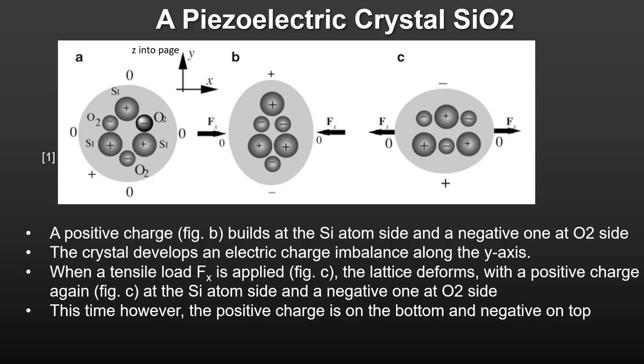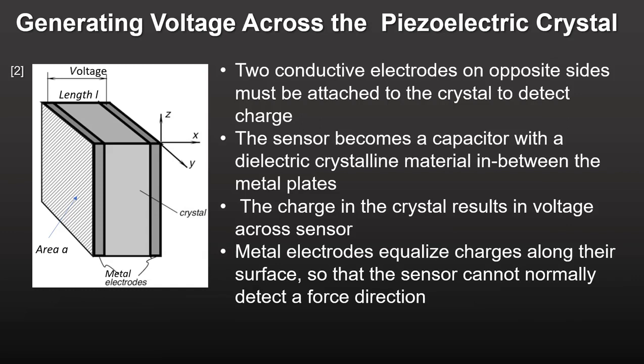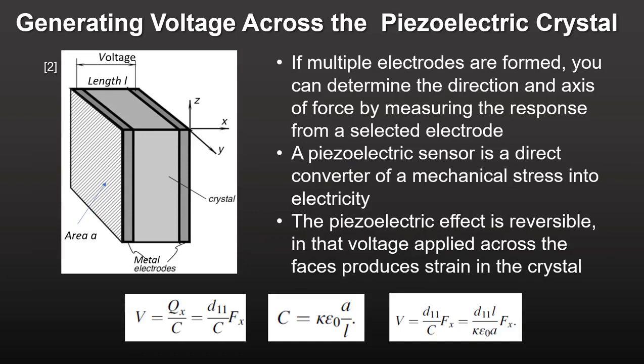You get negative charge on the top and positive charge on the bottom. You can't measure the piezoelectric charge unless you attach conductive electrodes to both ends of the crystal. When you do this, your piezoelectric crystal becomes a capacitor with a dielectric material in between the plates — the dielectric material is the crystal itself. The voltage across the electrodes is proportional to the force in the crystal. Because the electrodes equalize charges along the surface, the piezoelectric crystal cannot normally detect force direction. If electrodes are formed with a complex pattern, you can determine the location of the applied force by measuring the response from a selected electrode.